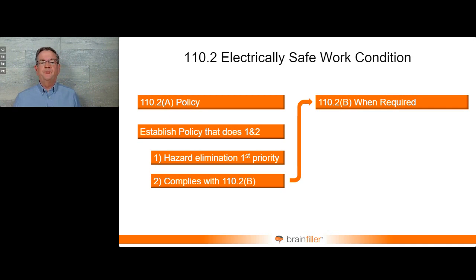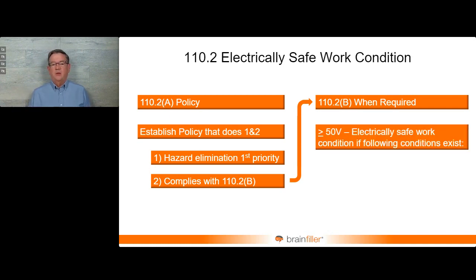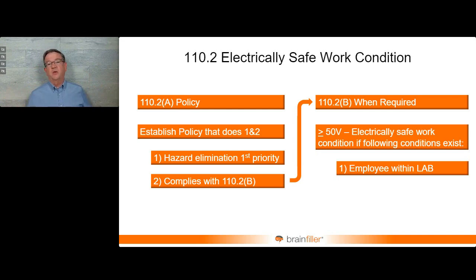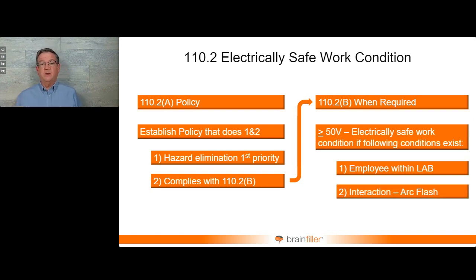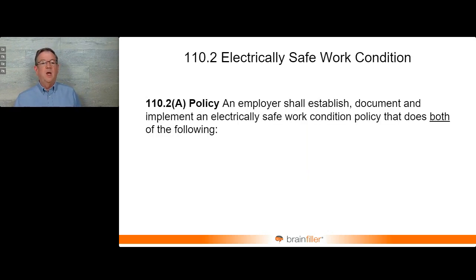When is this required? It's required when you're working on systems 50 volts or greater, and that aligns with OSHA as well, and the employee is working within the LAB. LAB is limited approach boundary. What that means, that's defined in NFPA 70E, is that if someone has exposed energized parts, there's a boundary where unqualified people have to remain back. So if somebody gets within that boundary and the parts are exposed, that is going to trigger the electrically safe work condition, or if there's interaction in such a way that may result in an arc flash. Interaction was actually introduced back in the 2009 edition of this.